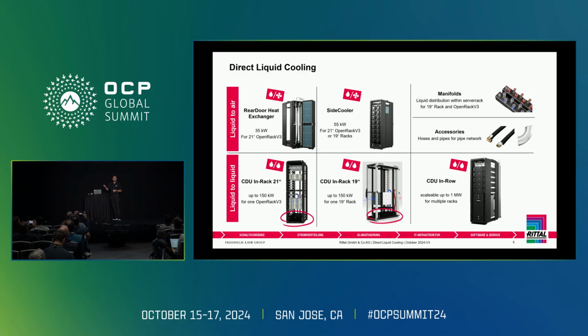And then going into liquid-to-liquid, we have CDU in-rack and CDU in-row. The in-rack is available in both form factors, 21-inch and 19-inch, and within that very small 4U footprint, 150 kilowatts of cooling capacity. As I've said before, it can be scaled right the way across to the in-row solution, which is 1 megawatt within an ORV3 rack.